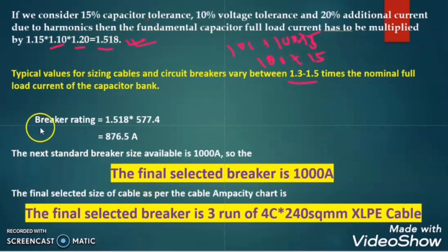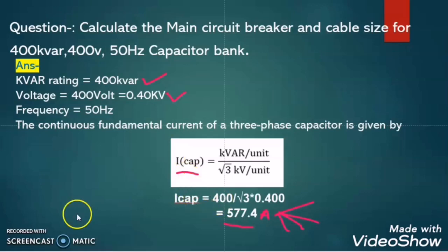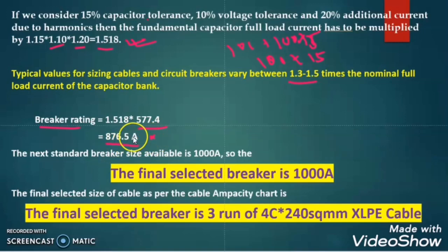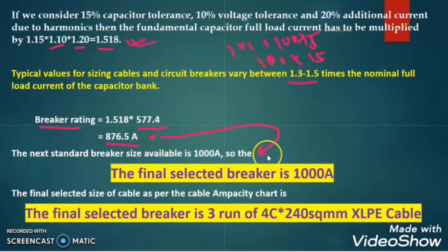So the final breaker rating will be the factor 1.518 multiplied by the capacitor current of 577.4 A, which gives 876.5 A. Since we cannot get this exact ampere rating, we go for the next standard breaker rating, that is a 1000A breaker.